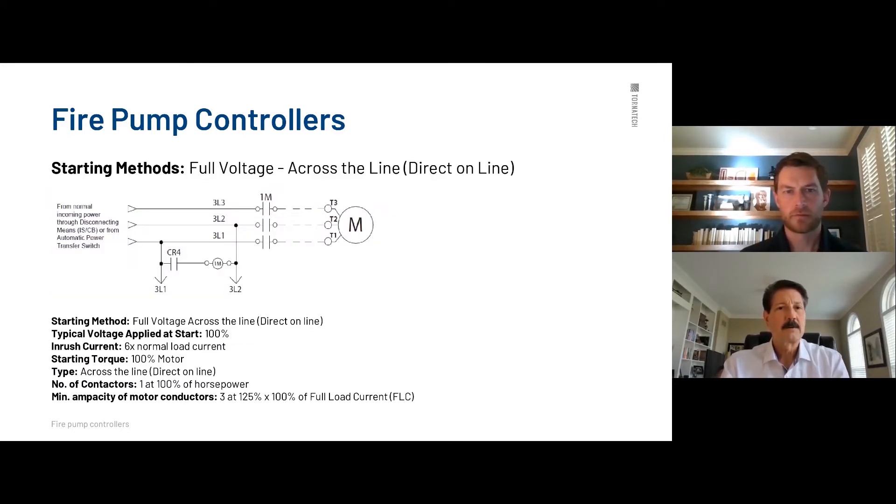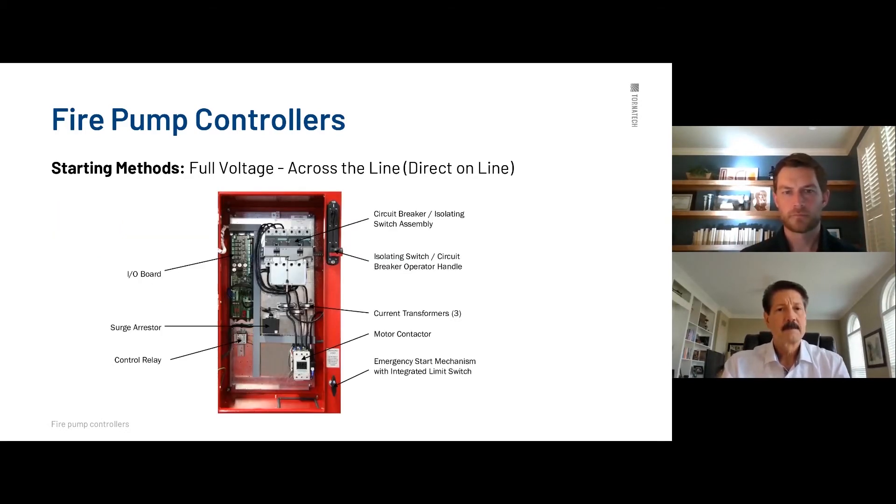So here we are across the line, full voltage. It's quite easy. Contactor opens and closes. Here's your three lines coming in. And again, T one, two, and three to your motor leads right here. It's very simple, very simple design. Internal components, pretty easy. Come in the top, loop up into the isolation switch here. It loops around through the magnetic breaker only down through the current transformers, which are sensing the amperage, draw the motor to the contactor right here. And this contactor is the workhorse.